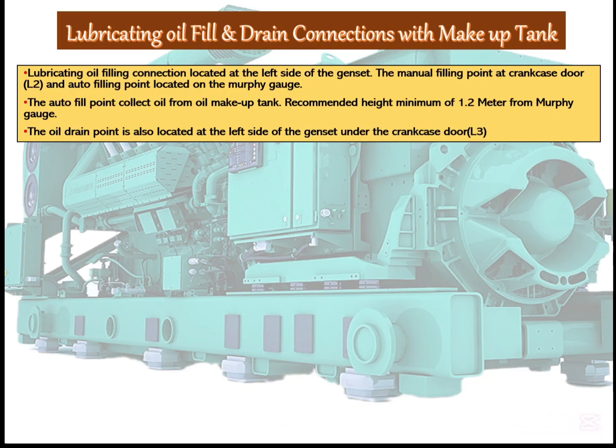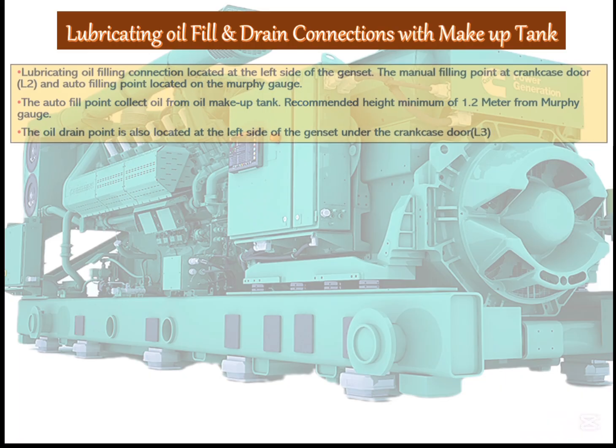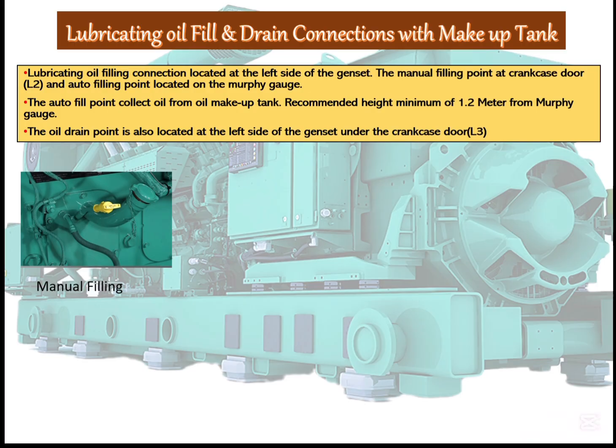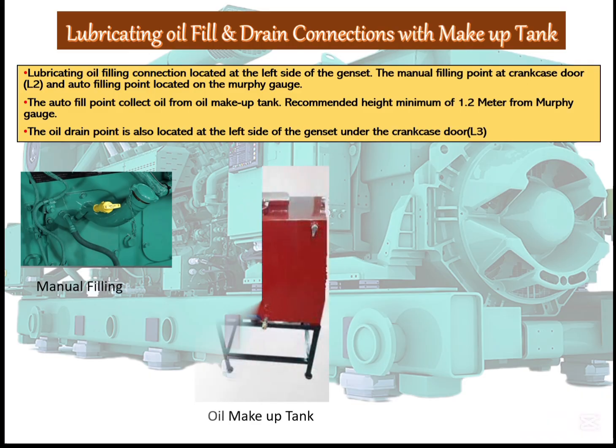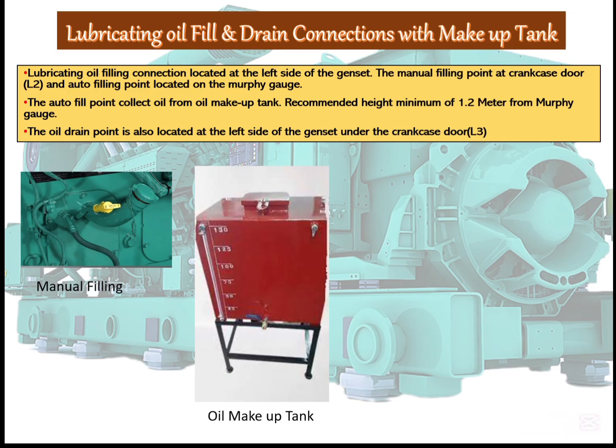Let's look at the lubricating oil fill and drain connection with the makeup tank. After cooling, oil is the next customer connection from the mechanical side. As I already mentioned, the manual or auto filling is located on the left bank L2 inspection door, where we have a depth gauge for level check. At the same point, we have manual filling, and we have a Murphy gauge for automatic oil level. This is the makeup tank. The recommendation for the makeup tank is a minimum 1.2 meter height, so the oil can come with gravity.